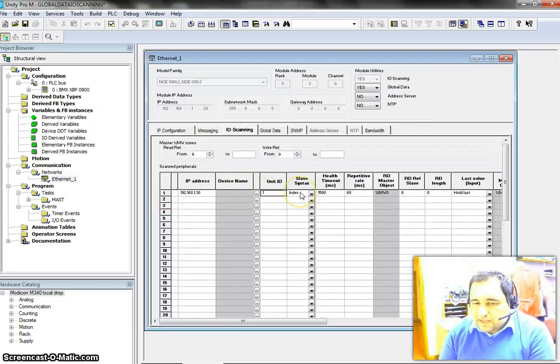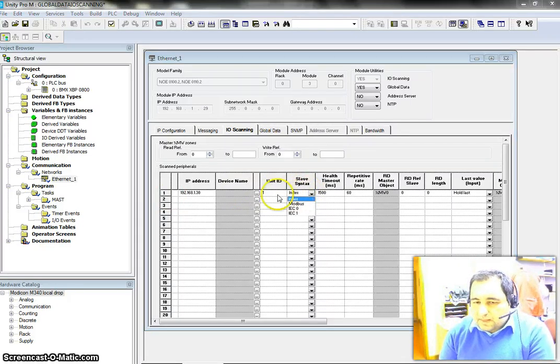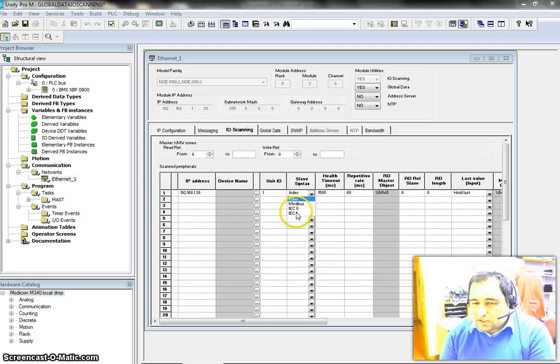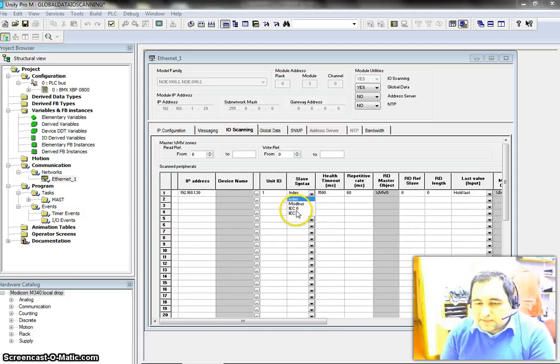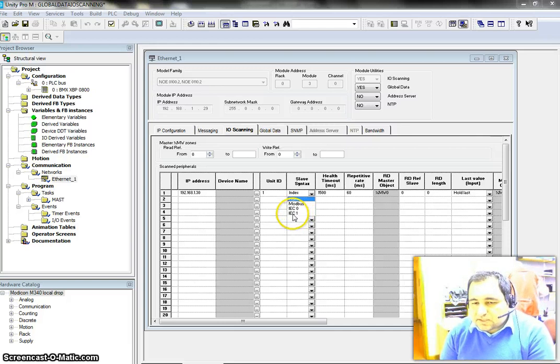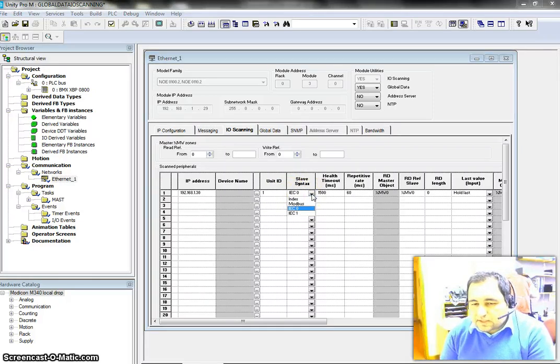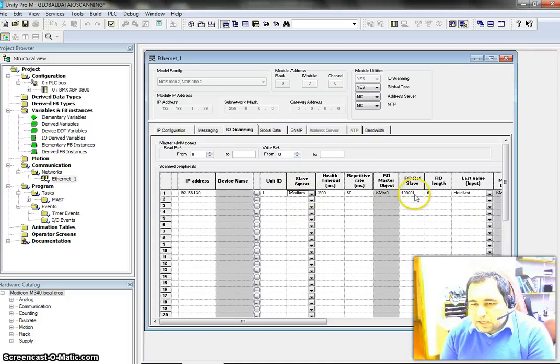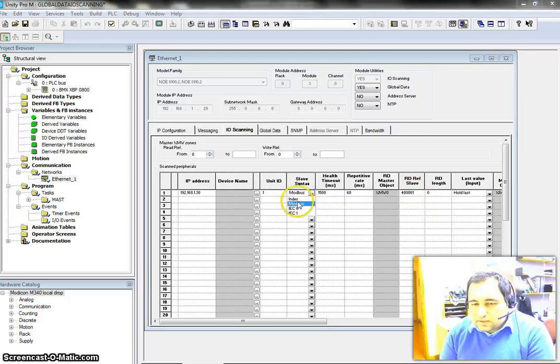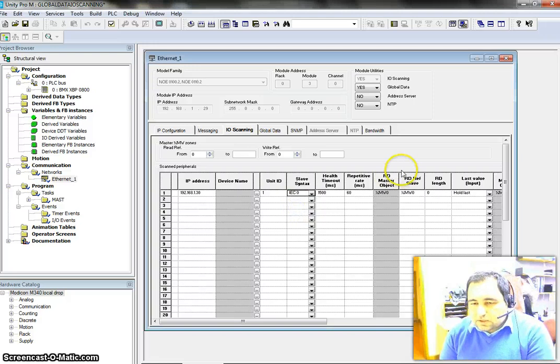After that, we have a slave syntax setting. We can have it as an index, or change it to Modbus, or IEC standard. There are two IEC standards: one starts registers with 0 and another starts registers with 1. In Unity Pro we use IEC 0. If you use Modbus, the number is formatted differently since Modbus starts with 1. Let's go back to IEC 0.